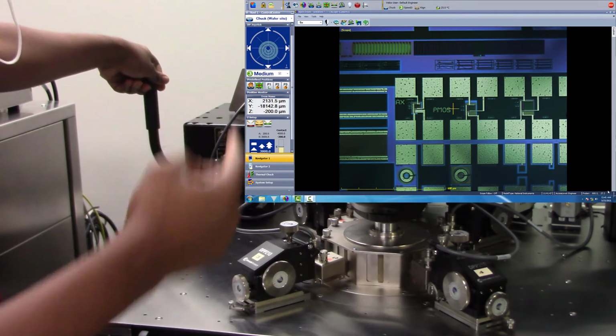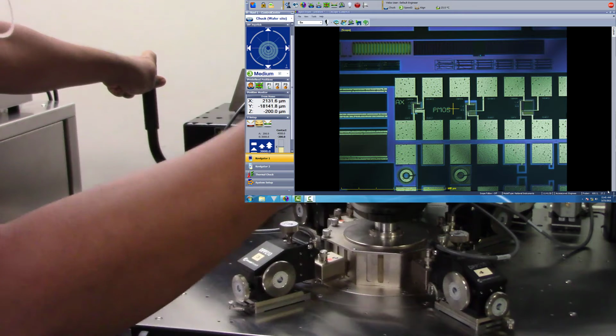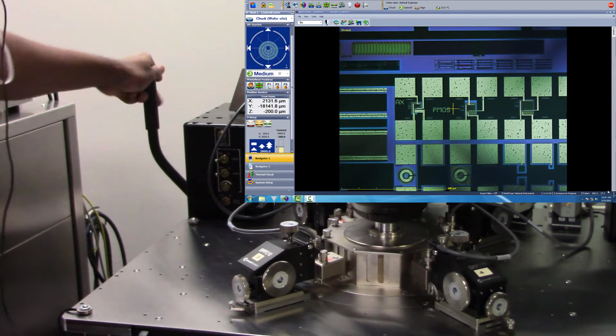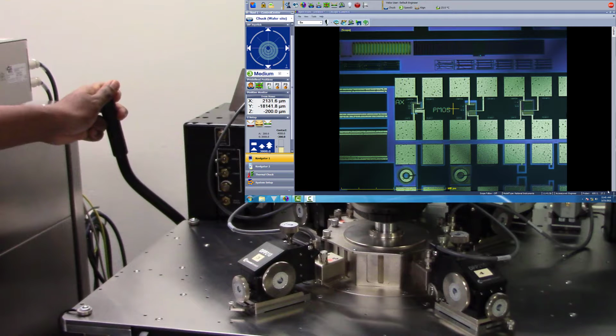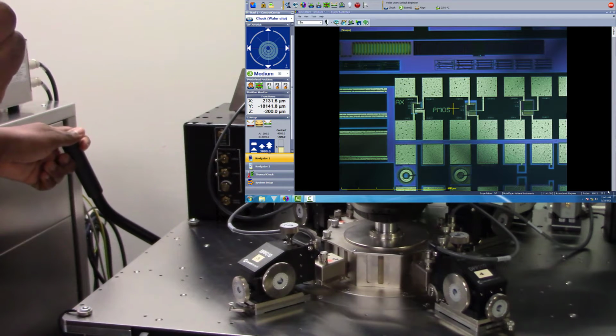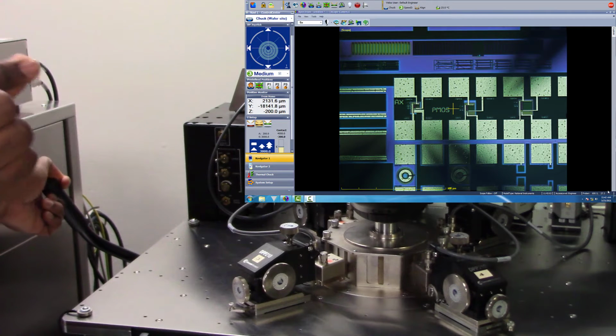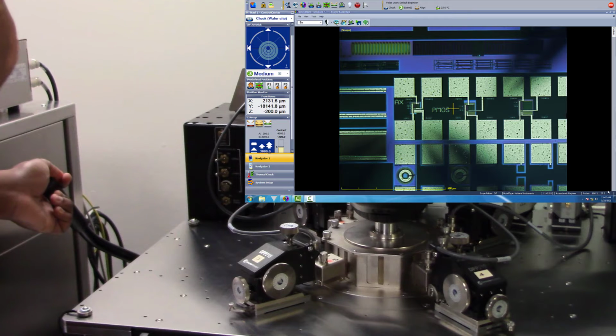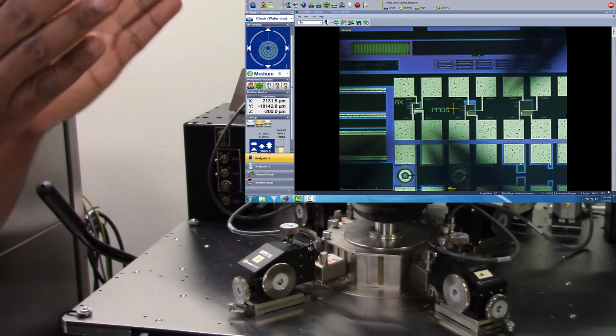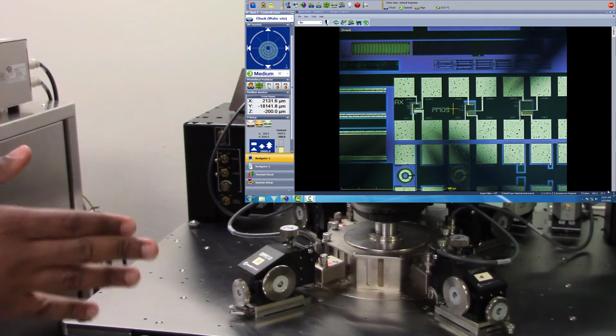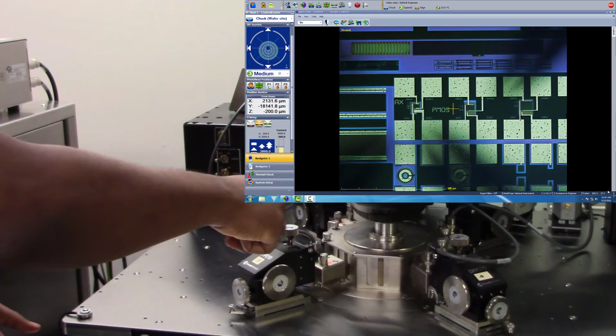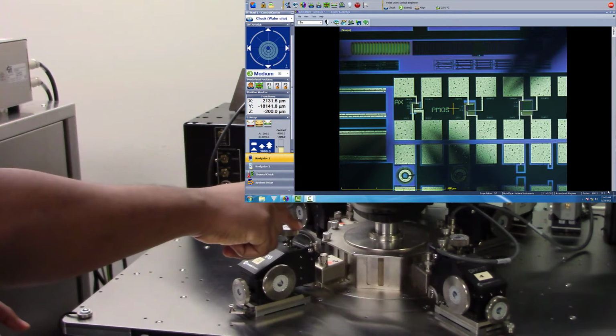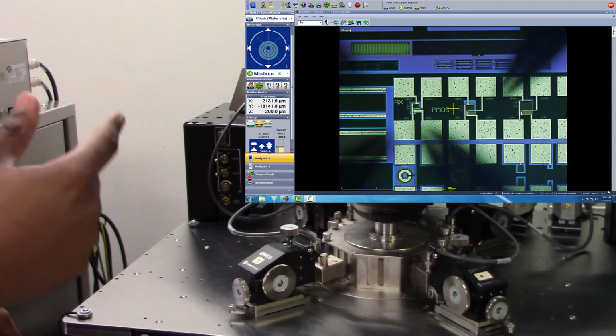So we're going to monitor this on the screen, both using the microscope lens and also using the screen on the desktop. So I'm going to slowly lower this down, and as we begin to lower it down, you begin to see the probe tips begin to come together. I usually describe it as you want to see something more like an open fish mouth. So once you see your probe tips coming together and becoming sharp, you need to rotate your Z position anti-clockwise so that your probe tips do not come in contact with your sample.